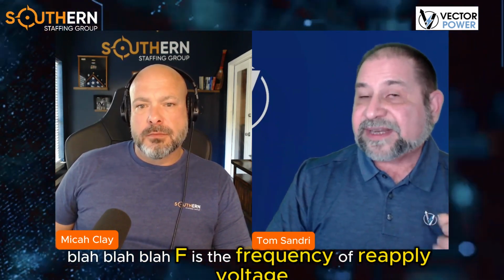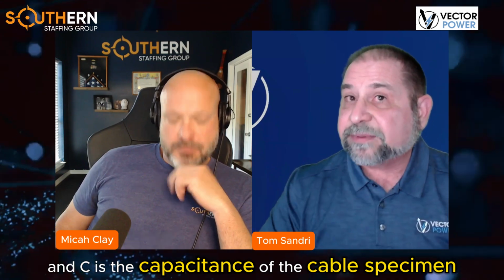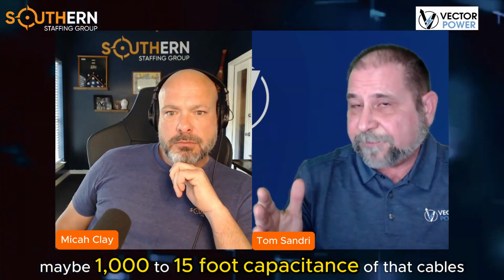In some of my presentations, I break the mathematics down. If you first want to learn what the capacitive reactance is, you would use the formula 1 divided by 2 pi F C. Pi, as we all know, is 3.14 and so on, so 2 pi is 6.28 and so on. F is the frequency of the applied voltage, so we could put 60 hertz in there, and C is the capacitance of the cable specimen that I'm going to test. So let's just say we were doing 15 kV cable of about maybe 1,000 to 1,500 feet.